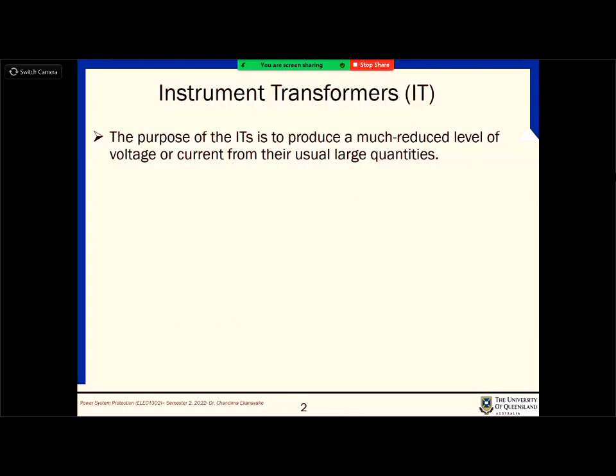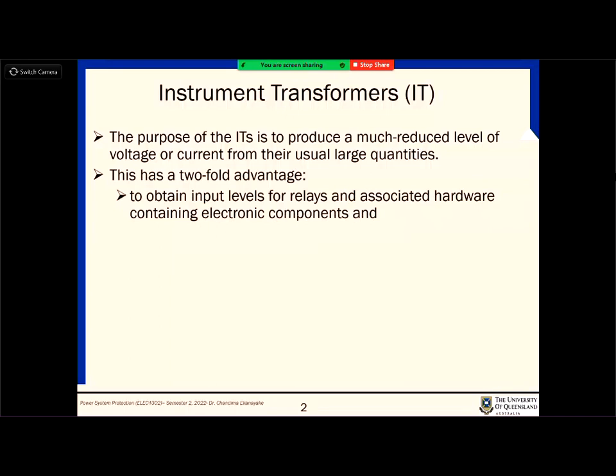The purpose of having them is that you need to have a safe level of measurements, and you want to isolate the primary circuit and the secondary measuring circuit, right? Because primary circuits involve very, very high voltage levels, but our instruments, usually electronic instruments, prefer lower voltage levels. The advantage is that you obtain input levels for relays and, as I said, associated hardware containing electronic components. Because electronic components need lower voltage levels, that's how we supply it through the ITs.